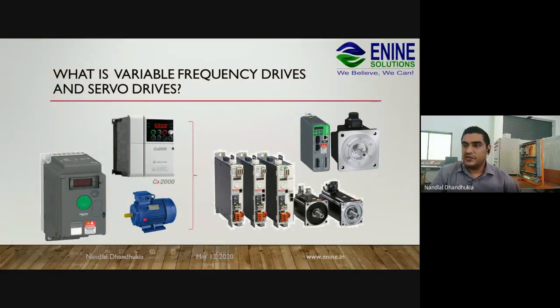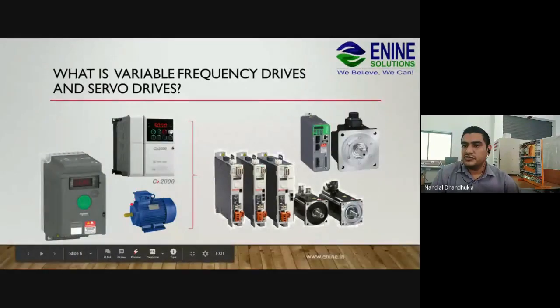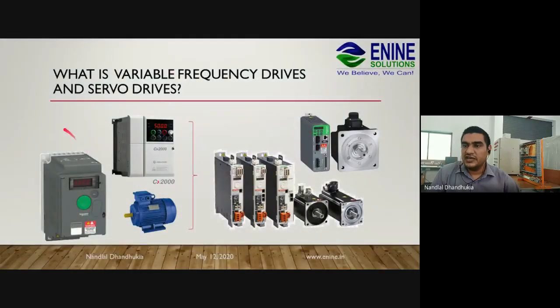So what we can do, we can use variable frequency drives and some sensor and the pump. Now the sensor will give us the feedback, okay, what is the pressure in the pipeline. So suppose you have set the pressure to 3 bar. Now your PLC will take the decision that, okay, the required pressure is the 3 bar. So when the pressure increases, the PLC will give command to the variable frequency drive to decrease the speed of the pump. So the pressure will again decrease.